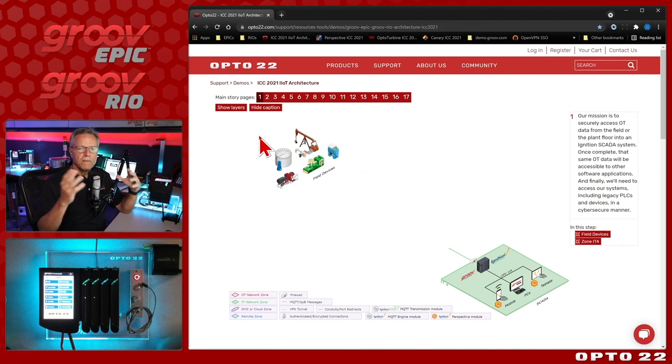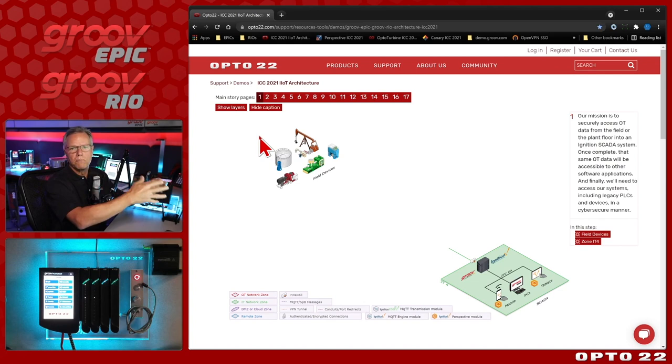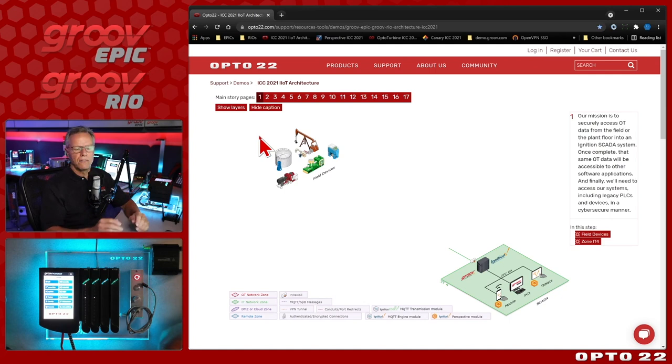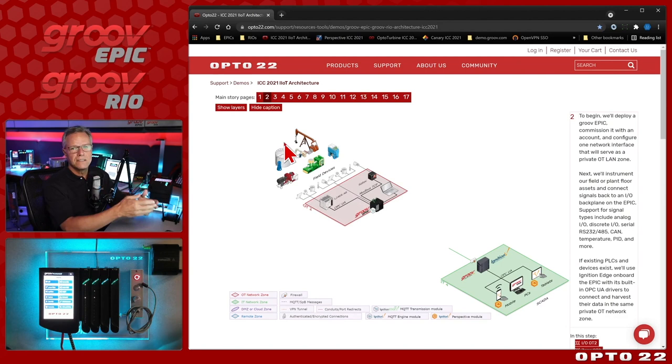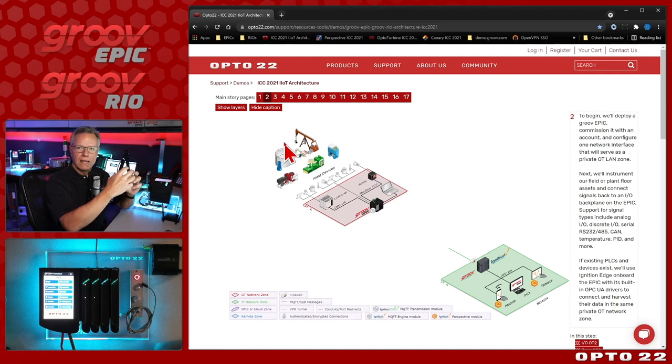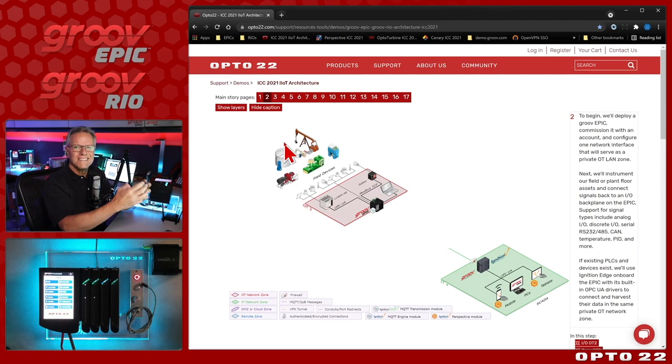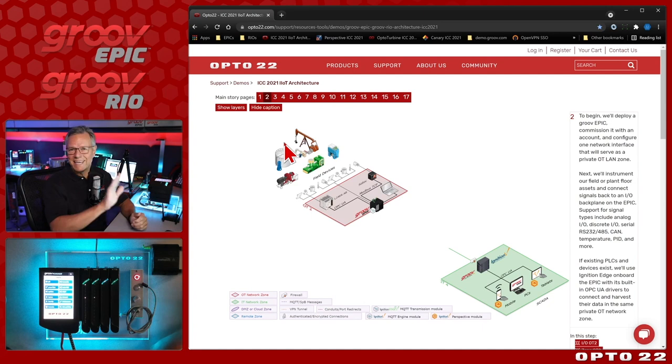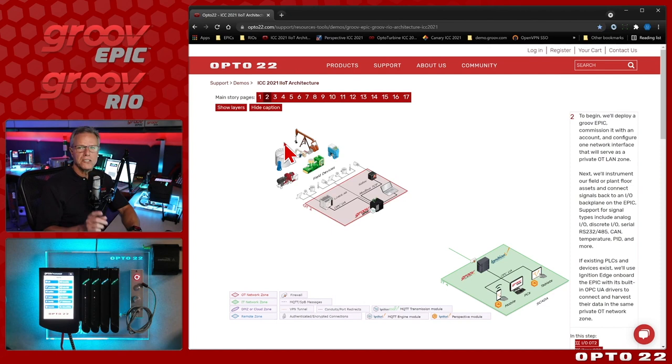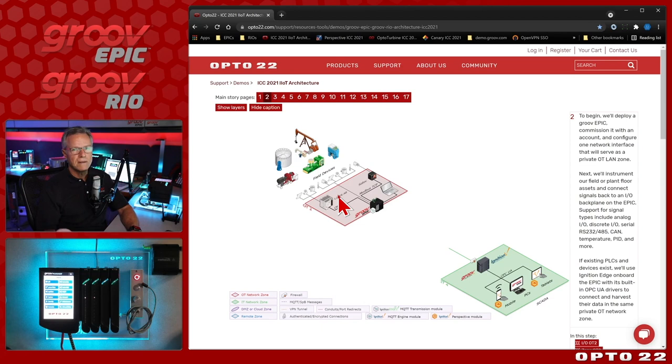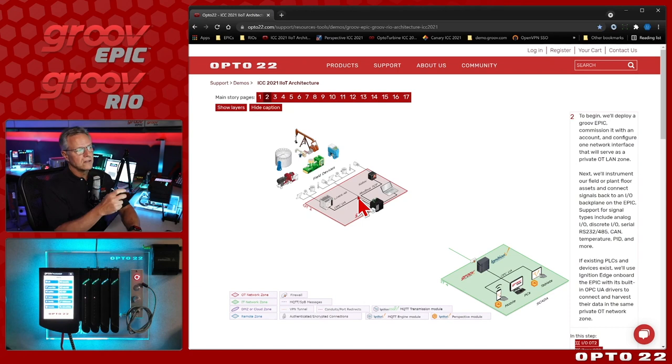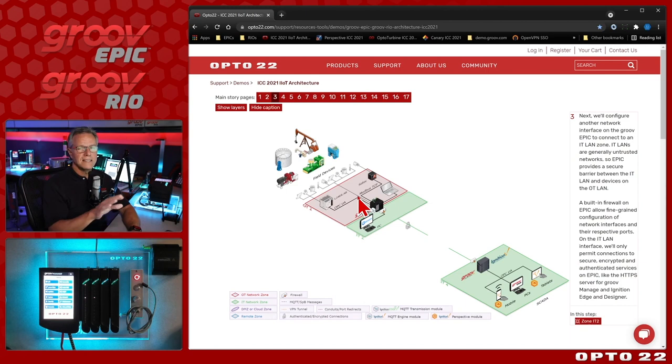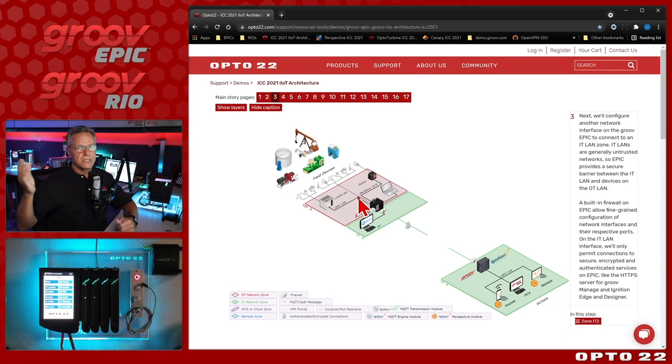Obviously, we'll start with the mission: how do we get field devices, whether they're in the remote field or on the plant floor, into Ignition SCADA while protecting those systems? The first thing we'll do is deploy an Epic into the field, and then create an OT zone LAN. This is what we're going to call a trusted network - that means we know everybody and all the devices on that network. This would be a private network with no exposures to the internet. It can't get out to the internet or to other networks and won't allow access in unless permitted specifically. We'll put the other devices on there - an AB PLC, a Modbus TCP device. We have a nice protected zone here for connecting our existing brownfield devices.